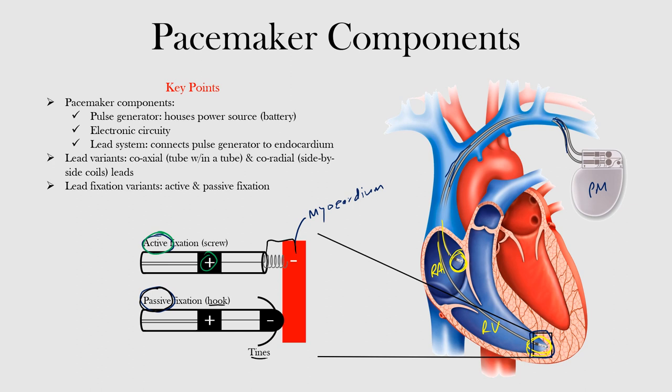Let's review what we discussed. The basic pacemaker components include the pulse generator, which houses the power source — the battery — the electronic circuitry, and different software and algorithms that each pacemaker may have. There is also the lead system that connects the pulse generator to the endocardium.